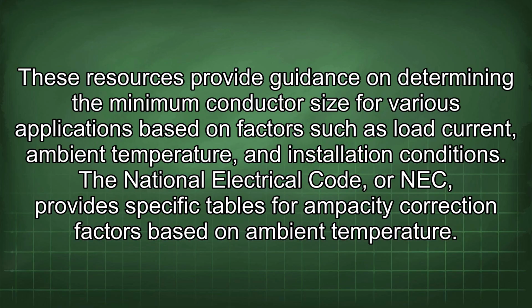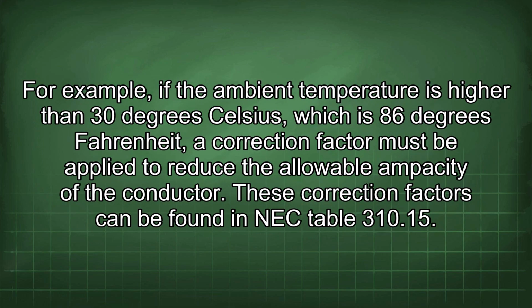The National Electrical Code, or NEC, provides specific tables for ampacity correction factors based on ambient temperature. For example, if the ambient temperature is higher than 30 degrees Celsius, which is 86 degrees Fahrenheit, a correction factor must be applied to reduce the allowable ampacity of the conductor. These correction factors can be found in NEC Table 310.15.